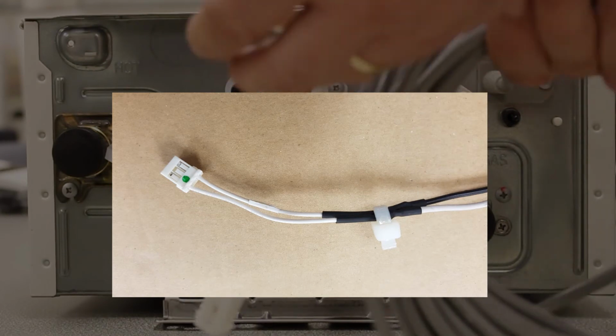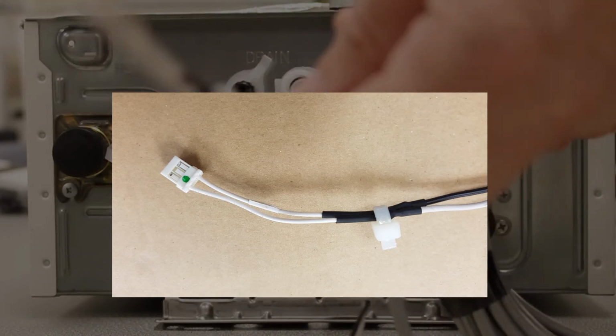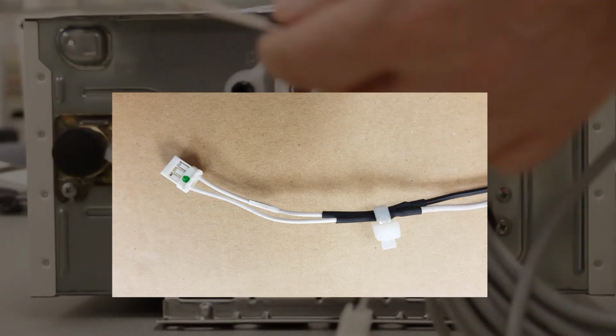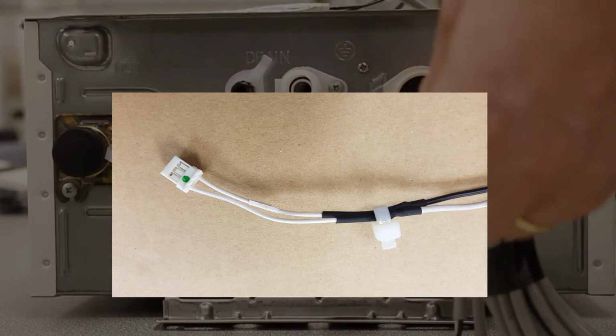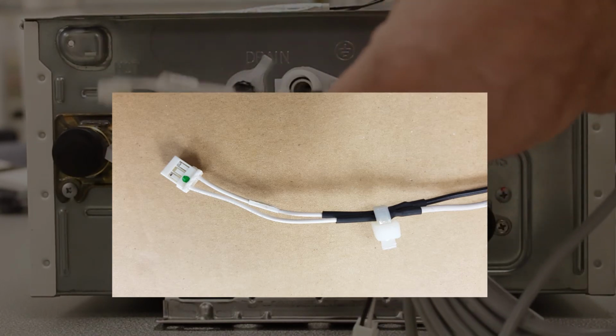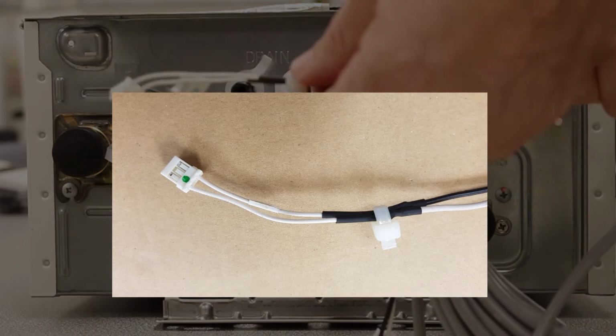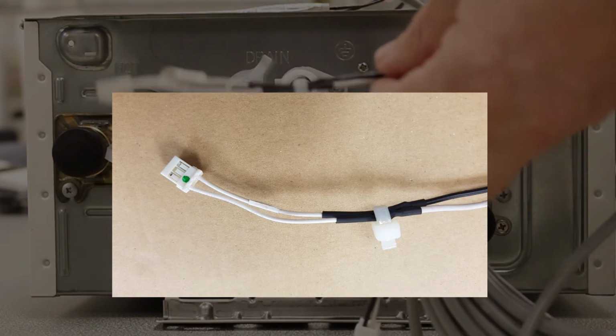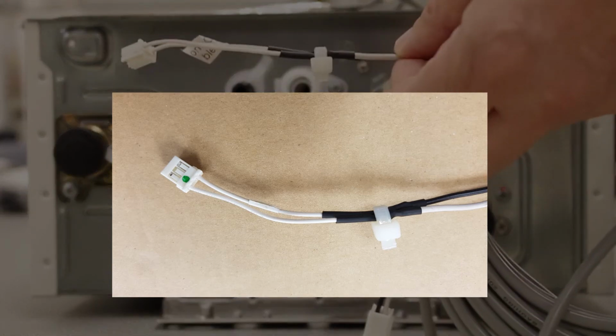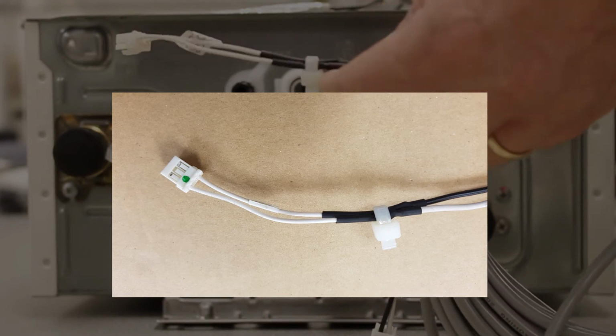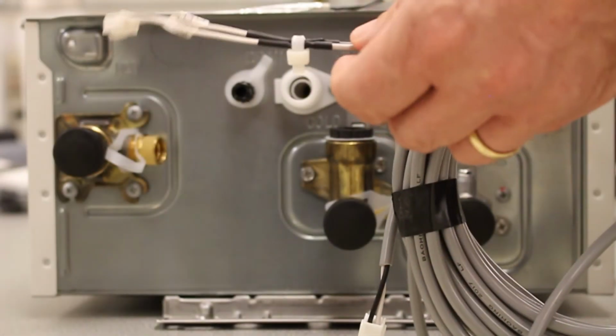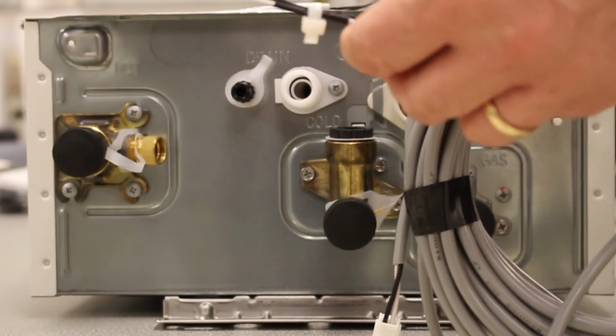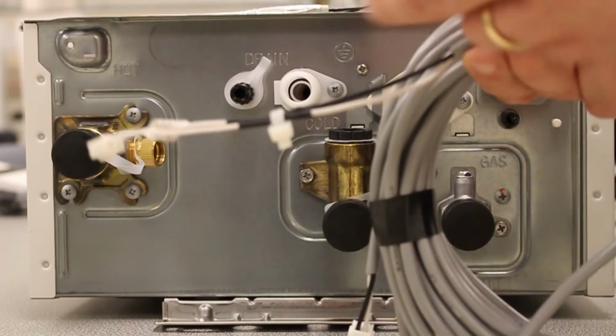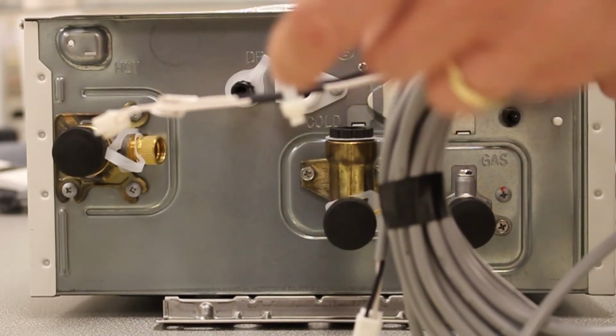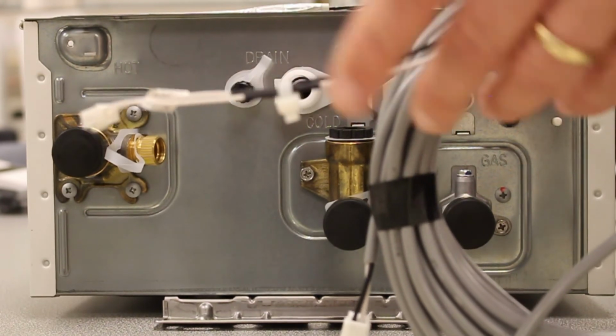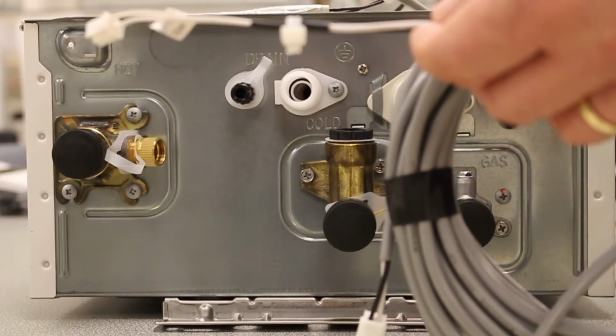So in this case we've connected the controller cable to the little plug that you get supplied, and we've done it in a sort of typically Rinnai fancy way. It's been soldered and it's had heat shrink put on. Now in the real world out there in the field, you're going to probably use some connectors for that, like top hat style or whatever, chocky block style connector. That's all good. Now polarity wise there's no problem, you can connect either wire to either side, there's no polarity on controllers, we don't have to worry about that.